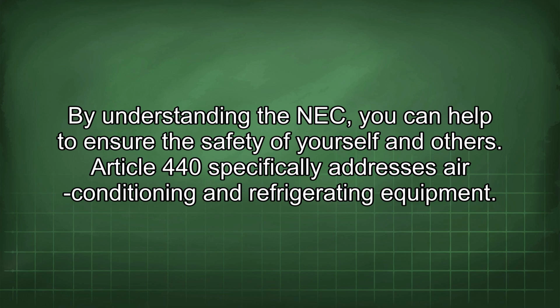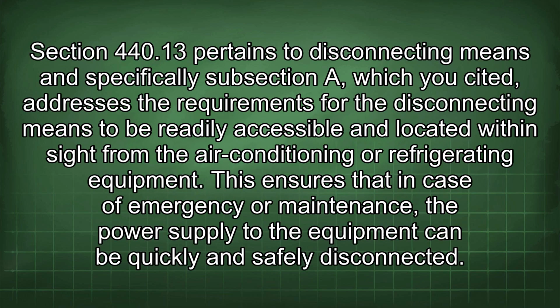Article 440 specifically addresses air conditioning and refrigerating equipment. Section 440.13 pertains to disconnecting means, and specifically subsection A, which you cited, addresses the requirements for the disconnecting means to be readily accessible and located within sight from the air conditioning or refrigerating equipment.